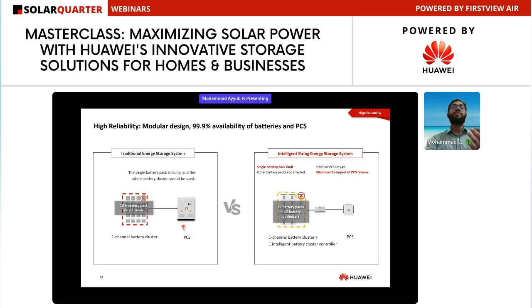The problem with a large PCS capacity is that if one PCS fails, not only is that PCS down, but the entire battery capacity connected to it is also down. So you can't utilize the batteries or the PCS, and you get a huge power loss in one shot. That's the advantage of the string concept—for both solar and storage products we prefer the string-level concept, because it avoids mismatch losses and gives a highly reliable power supply.